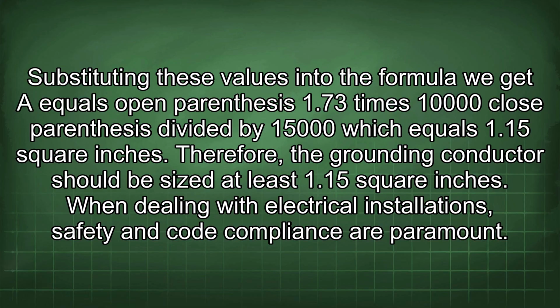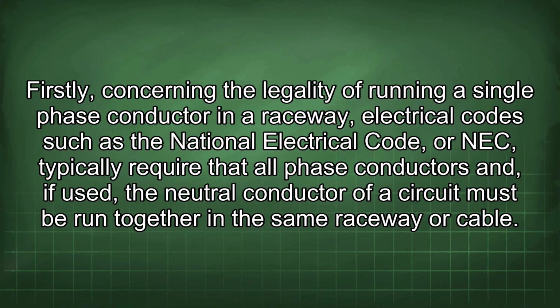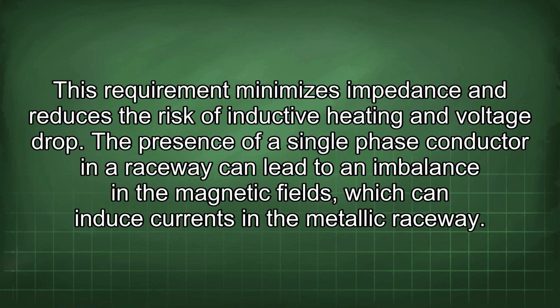When dealing with electrical installations, safety and code compliance are paramount. Firstly, concerning the legality of running a single-phase conductor in a raceway, electrical codes such as the National Electrical Code, or NEC, typically require that all phase conductors and, if used, the neutral conductor of a circuit must be run together in the same raceway or cable. This requirement minimizes impedance and reduces the risk of inductive heating and voltage drop.